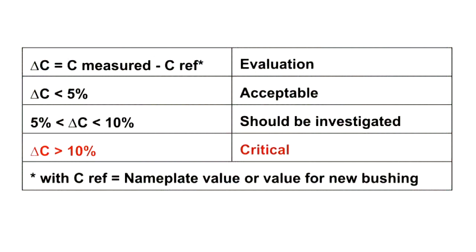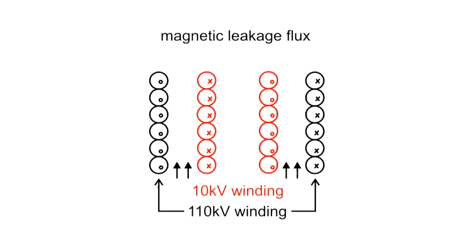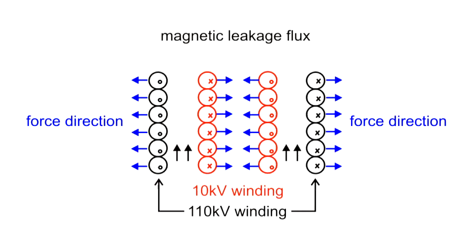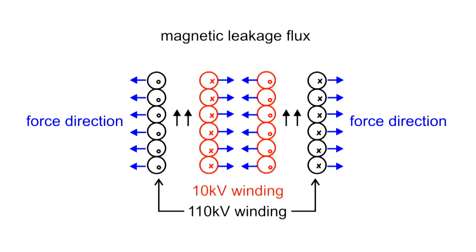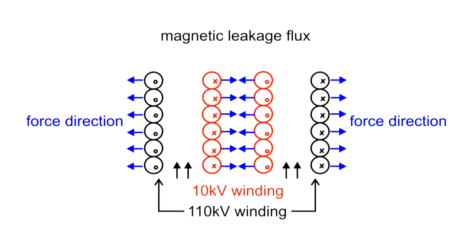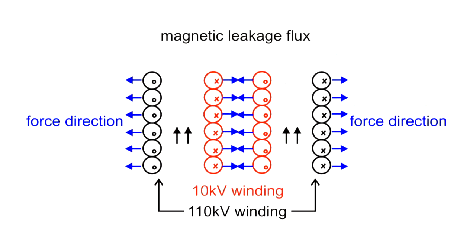For transformer windings, changes in capacitance between the windings indicate a change in the leakage gap. This gap can change due to the deformations caused by high short circuit currents and their corresponding forces.